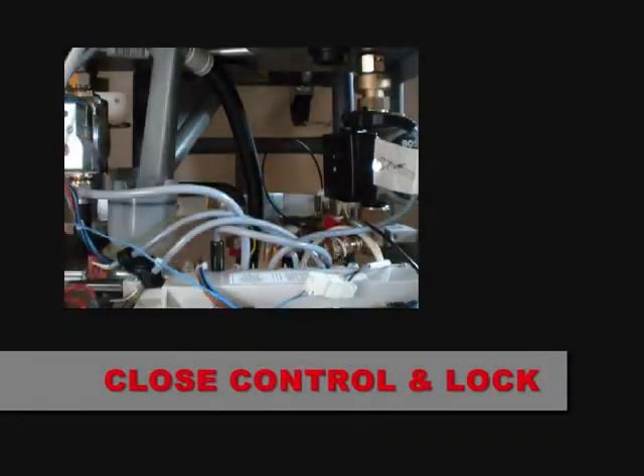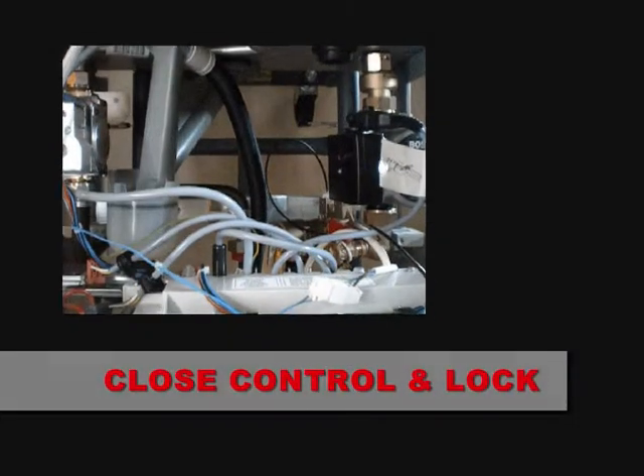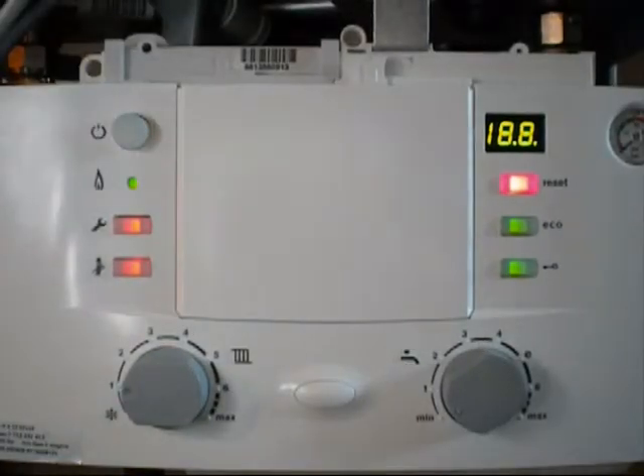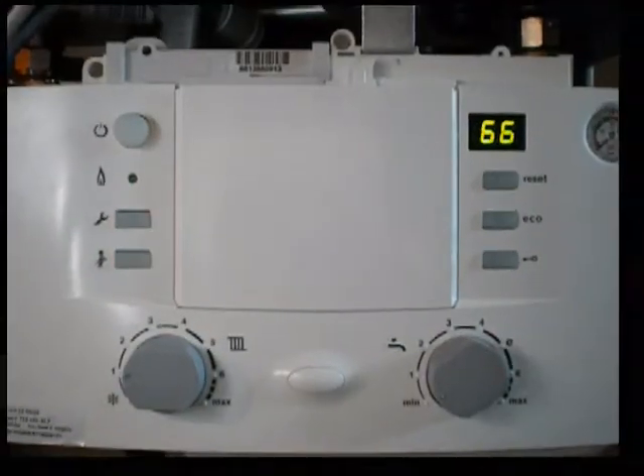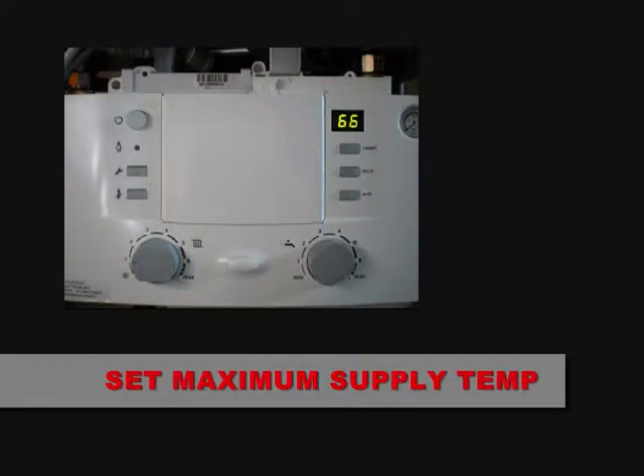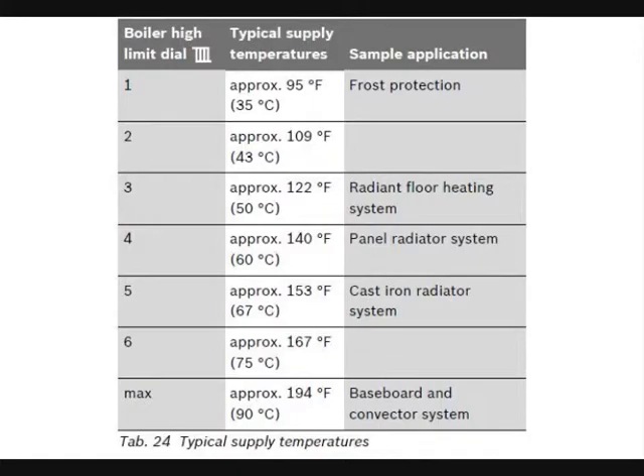Once the system supply temperature sensor is installed, close and lock the control cover in place. Power up the boiler. Then set your maximum supply temperature using the space heating dial located to the left on the control face. The numbers on the dial correspond to typical supply temperatures shown in Table 24 on page 60 of the install manual. Recommended temperature settings for different types of applications can be found there as well.